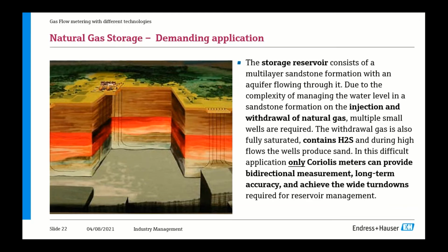Also, one of the difficulties of this application is that once you pump out the gas, it's already fully saturated and even contains H2S, which is a very corrosive gas. And even during high flows, they will produce sand as well. So once again, that's why Coriolis is a big advantage in this kind of application. Next slide, please.